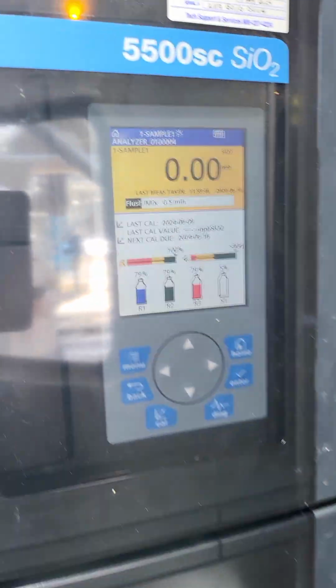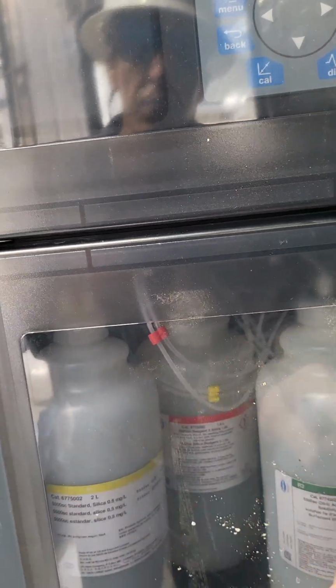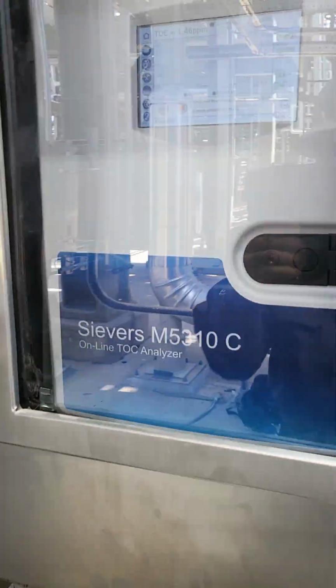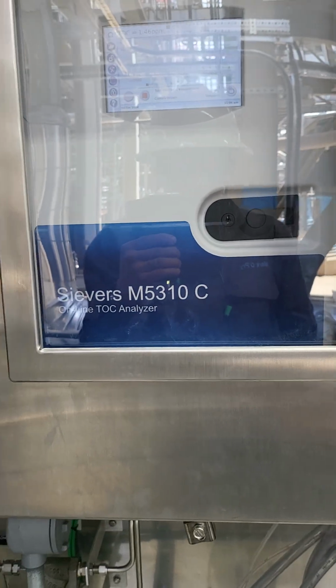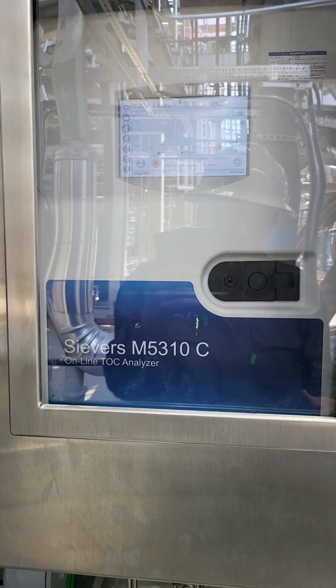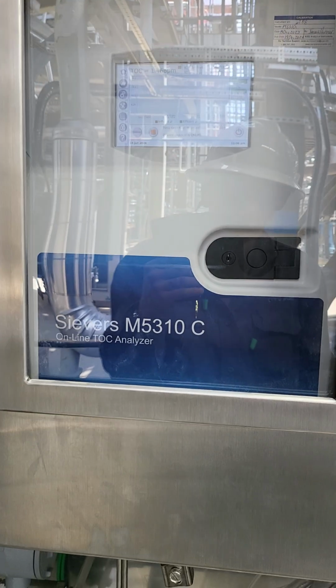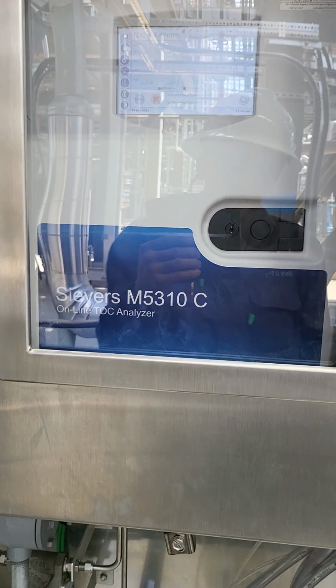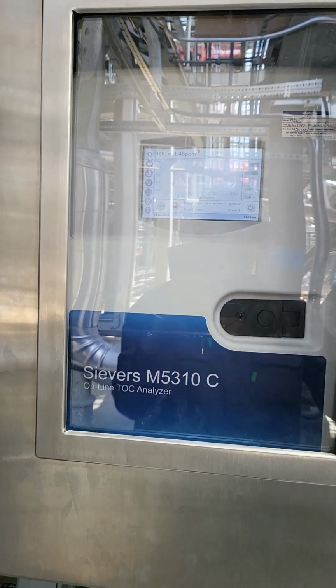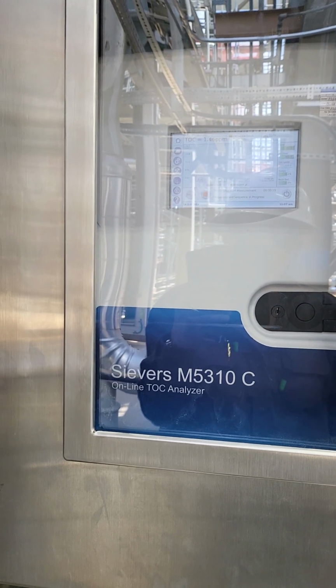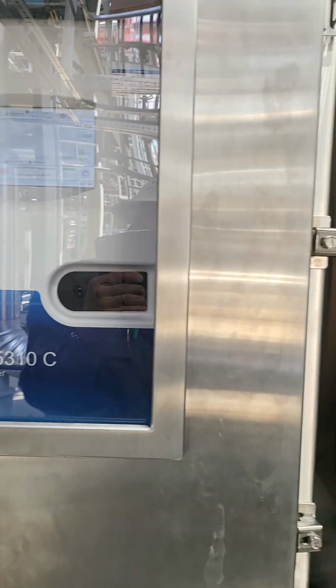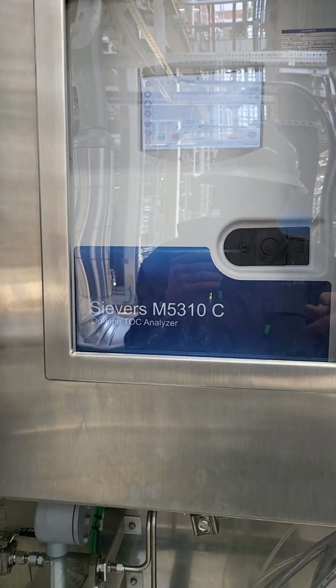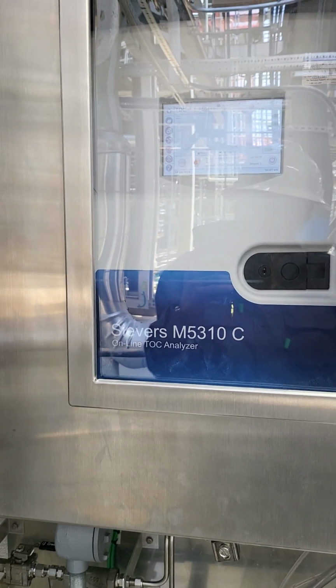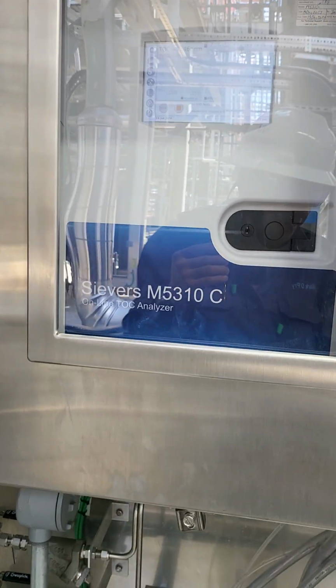All these water analyzers require different chemicals to operate. So basically, let's say the TOC, it has to have acid and base mixed in with the sample. The acid will attack the water. All of the total organic carbons will join with the acid and be forced into being CO2. The CO2 will travel up to a detector that measures only CO2, and the CO2 equivalent to total organic carbon is our output. Just for instance, every single inject that this does, it has to inject a certain amount of sample and a certain amount of acid, mix them together in the reactor, and then it starts all over again. They've got little peristaltic pumps that do the exact same thing.